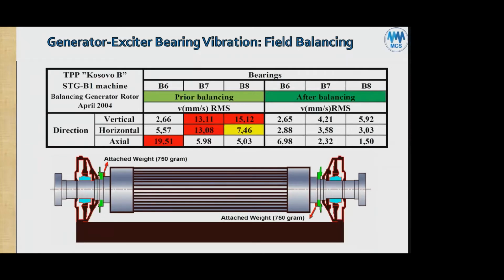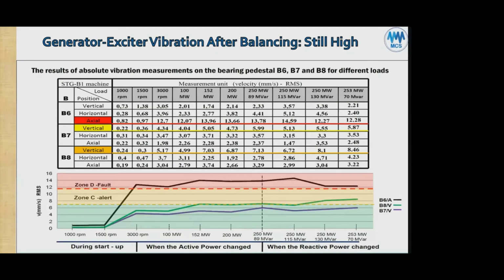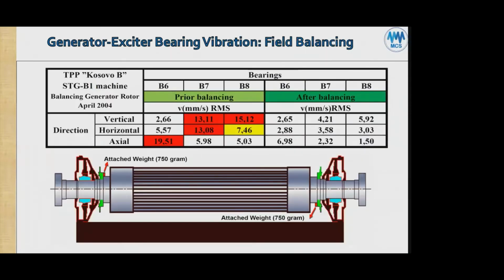Okay. So anyway, we end up here with 4.21 millimeters per second and 5.92. And the highest, which was the axial, was 19.51 millimeters per second. It dropped down to roughly 7 millimeters per second, which is kind of acceptable, yes. As a field balancing, it's acceptable. So when the machine was put back into service, unfortunately, it still had problems because they did what's called an unloaded balancing. The steam turbine is driving the generator at the rated speed of 3,000 RPM.